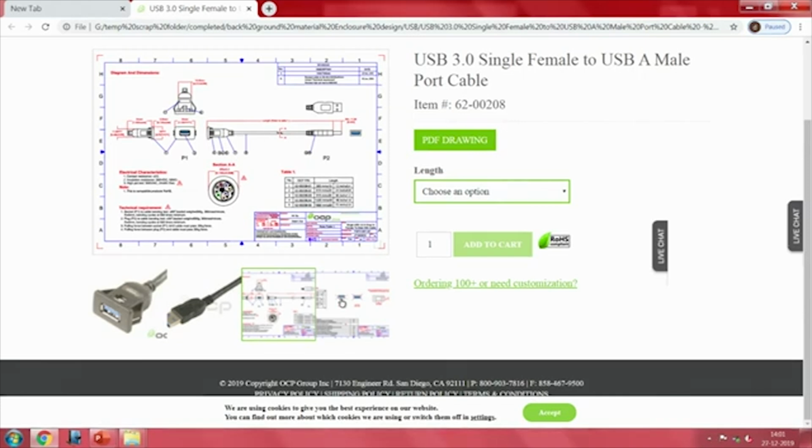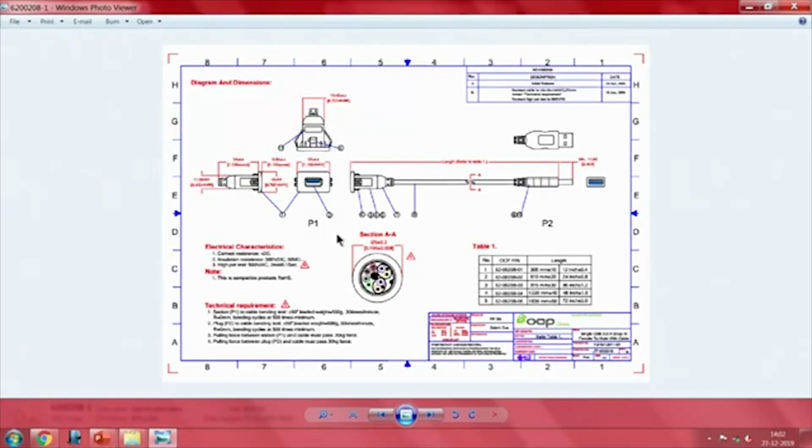So, there is a small wire which goes from the header and directly onto a panel. The panel will have a bulkhead mounted connector on both sides, and from there you take it outside. We end up with extra 4 or 5 potentially problematic pressure connections everywhere. So, in those cases probably we can take some wired connector and then directly solder it there, and then we can see here.